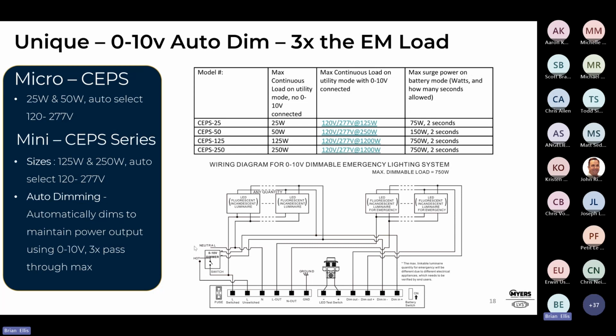When normal or utility power fails, all this stuff on the left goes away. The inverter outputs AC power, and it dims the 0 to 10 to 0 and slowly ramps up until it reaches its output wattage. So a 750 watt load with a 250 watt inverter is going to be roughly 33% light output. Now, one thing to note is this is only bypassing one lighting control zone. If you have more than one lighting control zone, then you have to move to a larger inverter and then the multiple bypass relays out in the space.